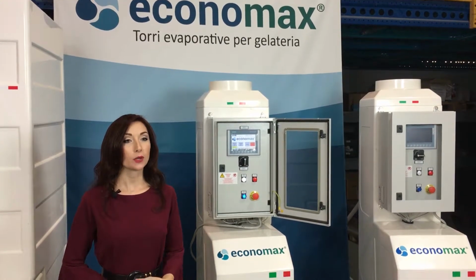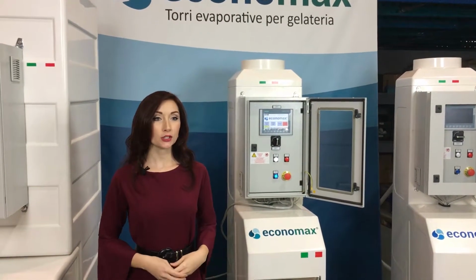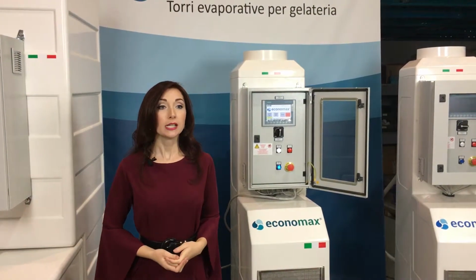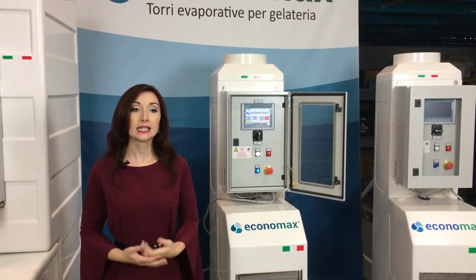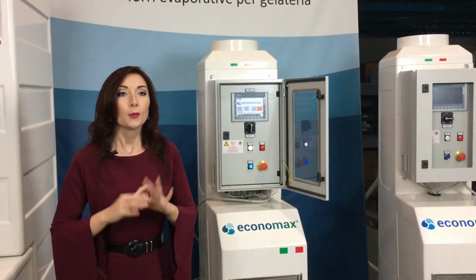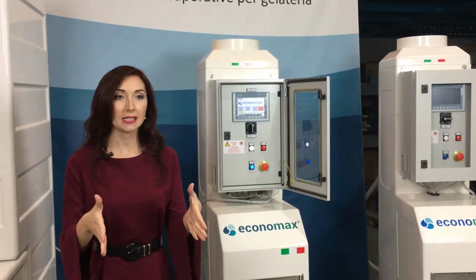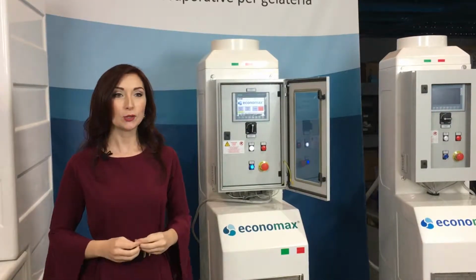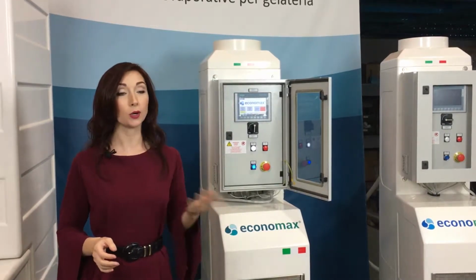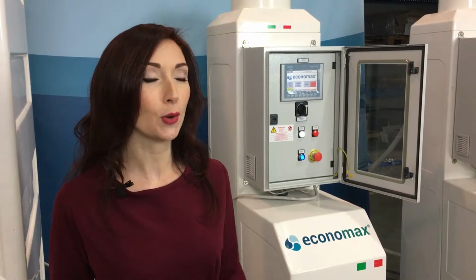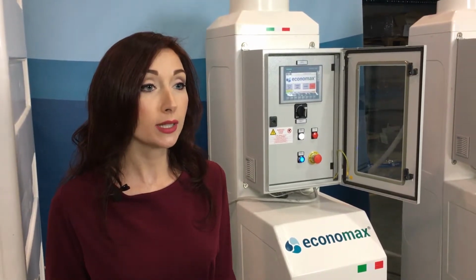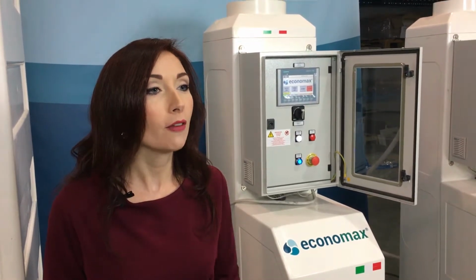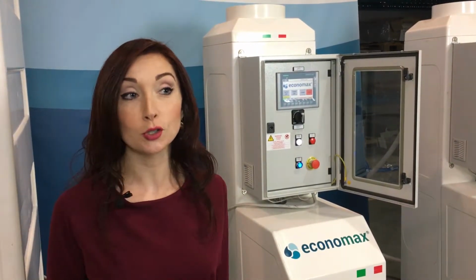Just like other industrial towers produced by Mita, ECONOMAX is fully created with lasting, non-corrodable materials, such as fiberglass used for the body and stainless steel for the supporting structure. Moreover, we designed the tower so that it is extremely compact and mounted on wheels. This allows you to easily position it inside or outside your workroom with no variation in its performances. The internal components, all of the highest quality, are fully managed by an inverter. This makes a great difference since it ensures very low energy consumption and it reduces noise emission to the minimum. You'll get rid of all of those annoying on and off noises of traditional solutions.